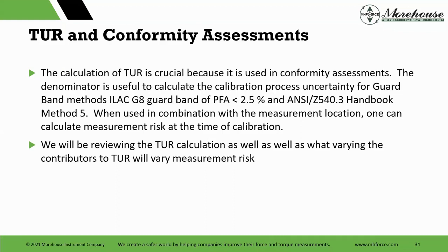So the denominator is useful in the TUR calculation to do other things. We can use it for method 5. We can use it to calculate our expanded uncertainty that we can report on our scope. So very useful, that denominator formula. So ILAC G8 can be used for that. ILAC G8 is a little bit different than the ANSI Z540 handbook because the ILAC G8 method says, hey, a PFA of less than 2.5%. ANSI Z540 says 2%.